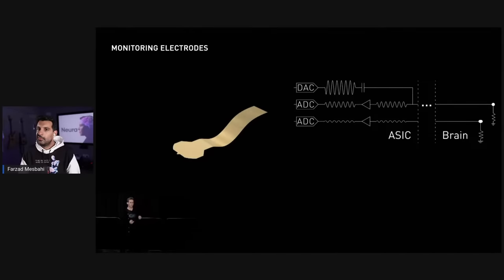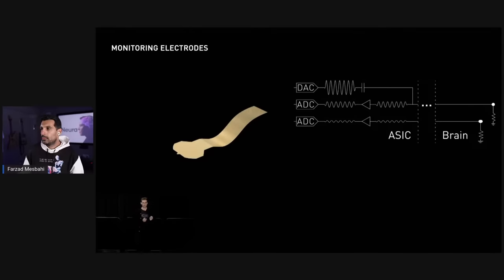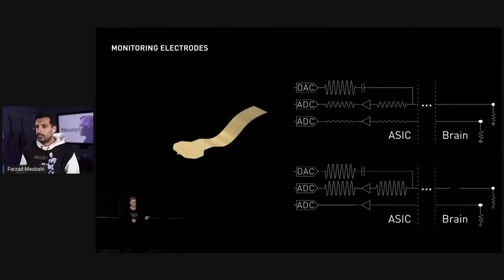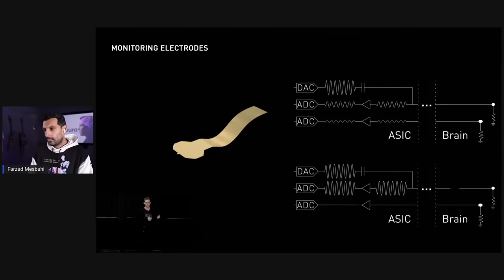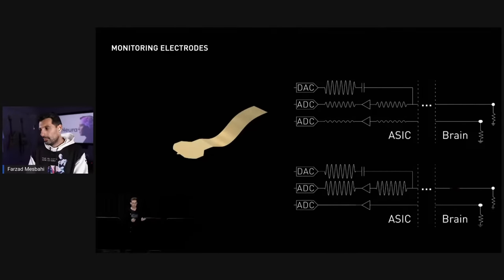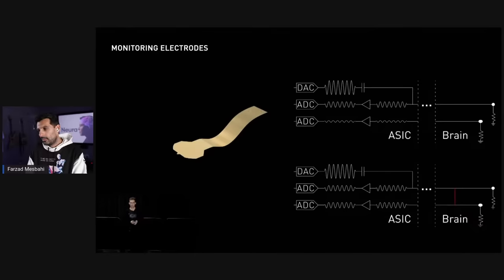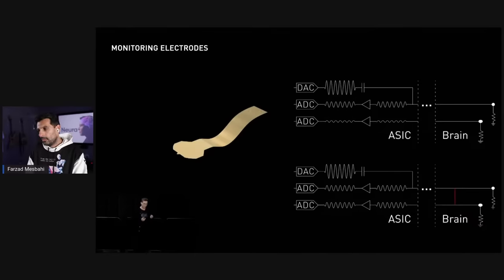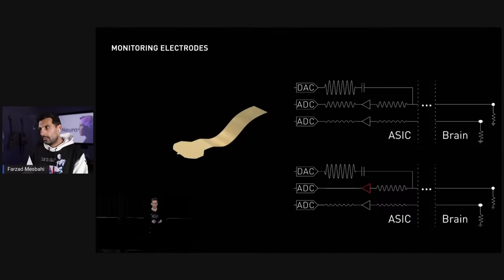Not only can we measure the impedance of every channel with this, but we can also map different physical phenomena to different characteristic signatures. For instance, an open channel will appear as a very large response on the channel, and shorted channels will appear as a large response on neighboring channels. By looking at the purity of the signal coming back, we can also validate that the analog front end of the neural sensor itself is operational.